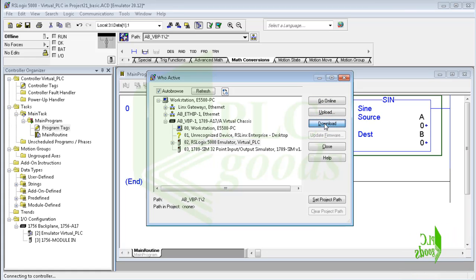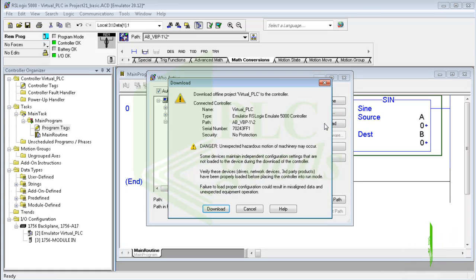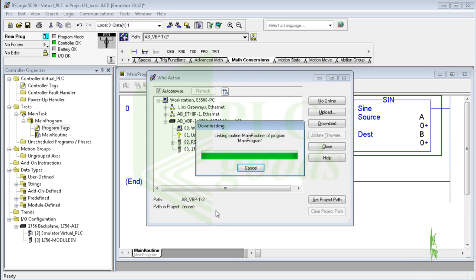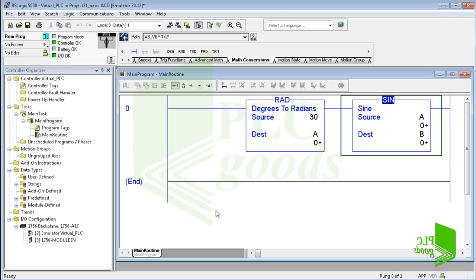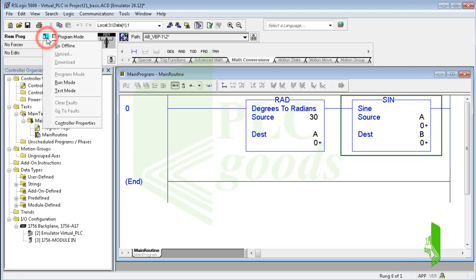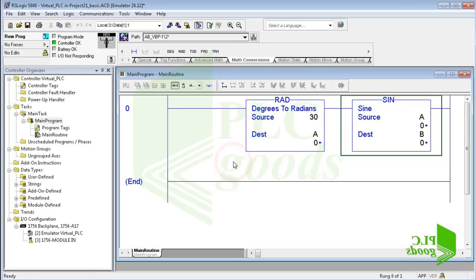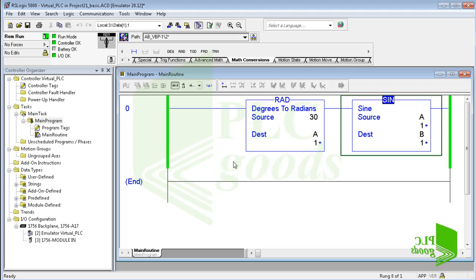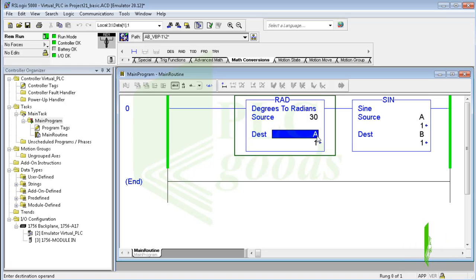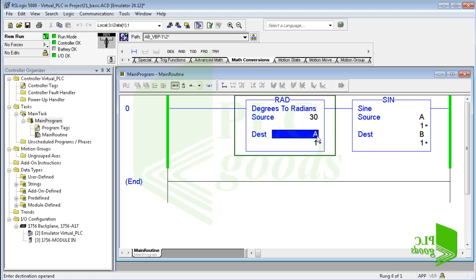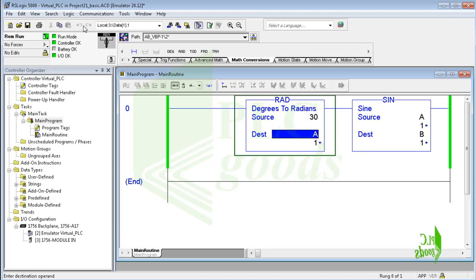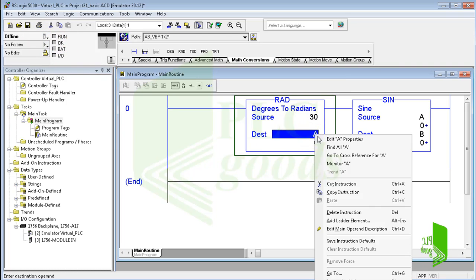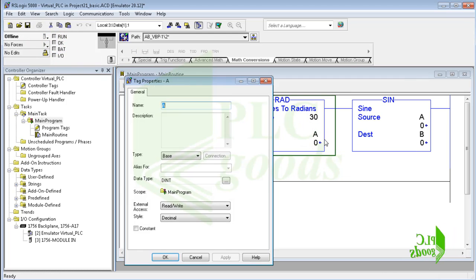Pay attention, as I mentioned before, data types of defined tags are important when we are using math instructions. Data types of the A and B tag are double integer. This data type is only used for integer numbers. But when we're using trigonometric functions like sine and radian, we need real numbers. As you see, the calculated value for A and then B are wrong, because the data type of the A tag is integer, which removes the fractional part of real numbers. So let me modify data types of the A and B tag and then test the program again to see the correct answer.